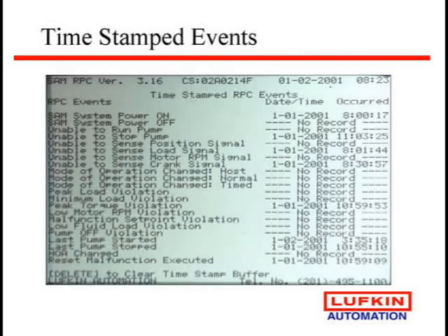Most all of them are smart units, so they can tell you and save data if the well's been stopped or not. You know, we've had a lot of things where a wild contract crew's running around working on pipelines and shutting wells off and on, and you don't know it. You'll know it with these systems. You can wire HOA up. So if anybody turns the controller off, you can get an immediate alarm and you know exactly what time it happened. So when the guy says, oh no, we didn't turn it off, well, mystery, huh?